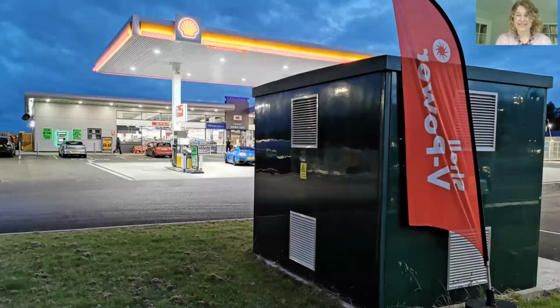This here is a substation that we have installed. It doesn't have the ongoing EV charger infrastructure here, which would be the LV panel and the charger units themselves, but it gives you a feel for the size of substation needed. We usually say they can be about 3 meters by 3 meters, but you have to allow a footprint of about 5 by 5 meters.